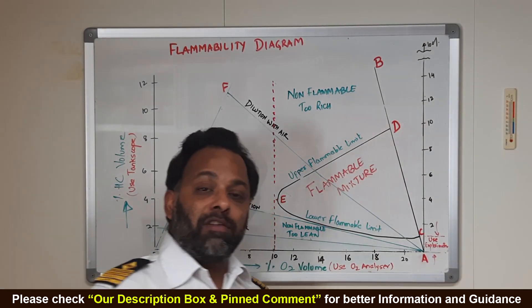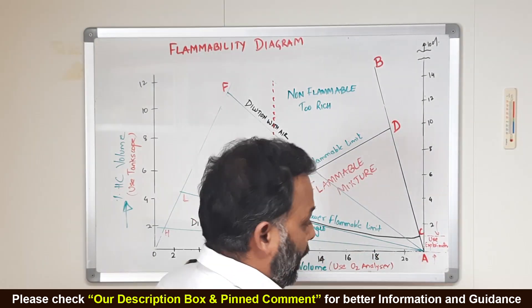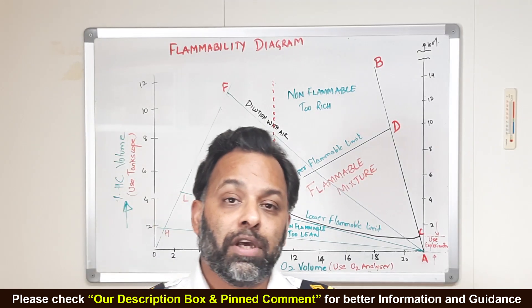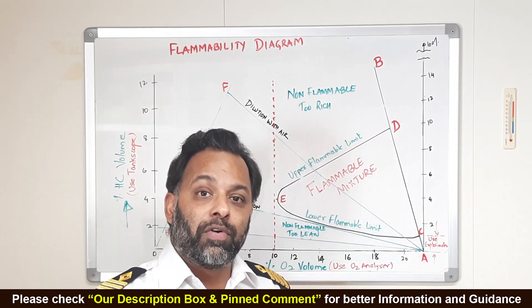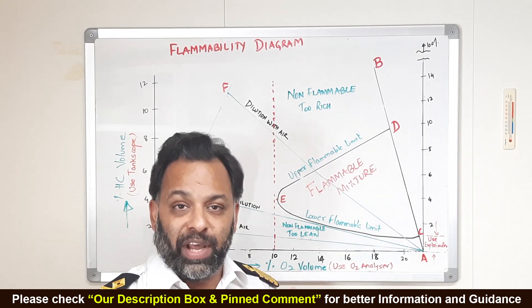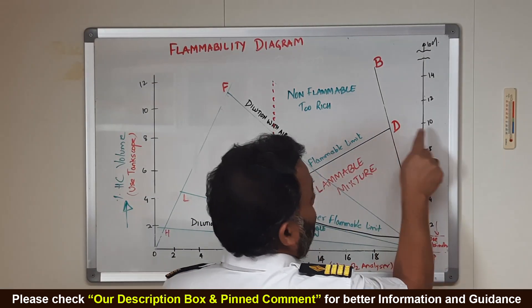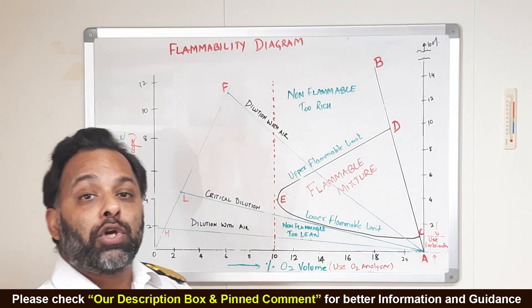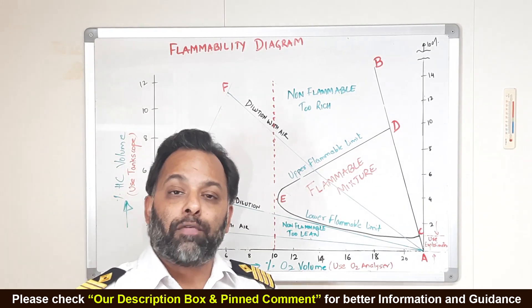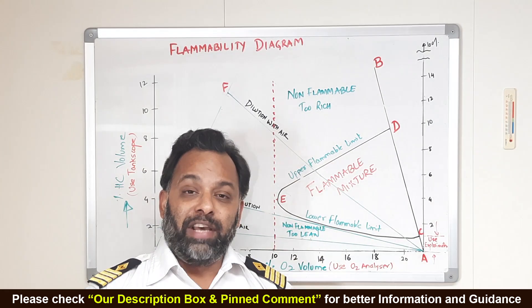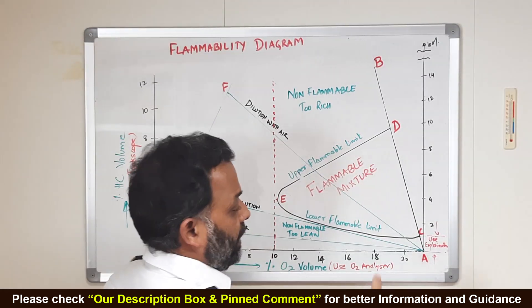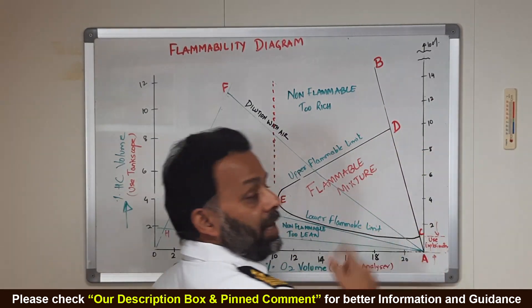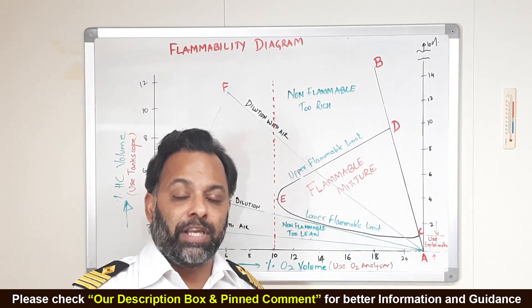For crude oil, upper flammable limit and lower flammable limit is 10% and 1% by volume of hydrocarbon respectively. What this means is, any mixture of hydrocarbon and oxygen below lower flammable limit, the mixture is too lean to fire. Anything above 10% of hydrocarbon by volume, this mixture is too rich to fire. That means, the amount of oxygen in this mixture is too less to sustain or to start a fire. Anything from point C to point D on this diagram is in the flammable range, explosive range, flammable region, flammable mixture.